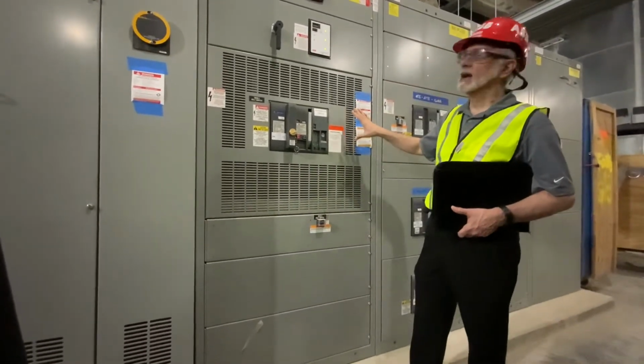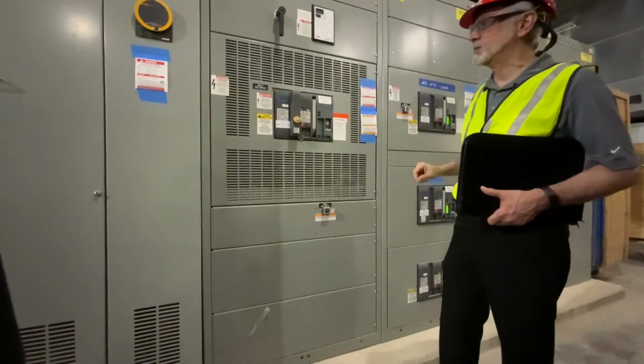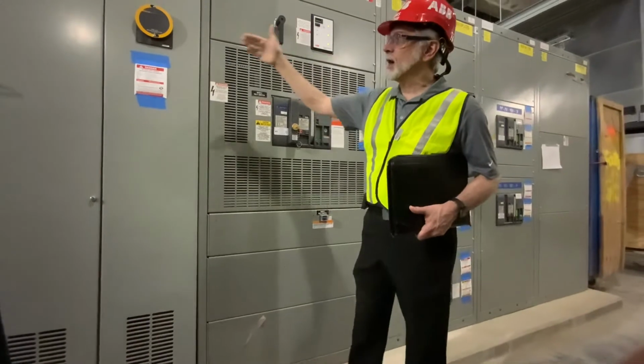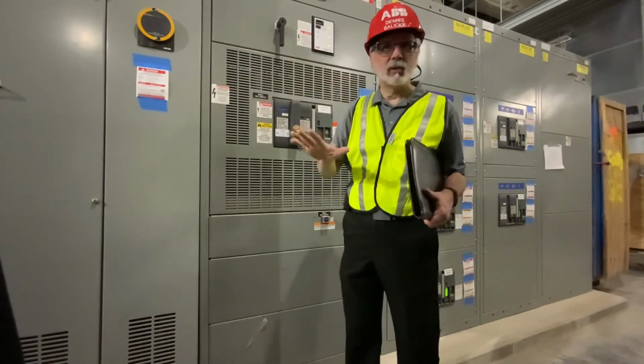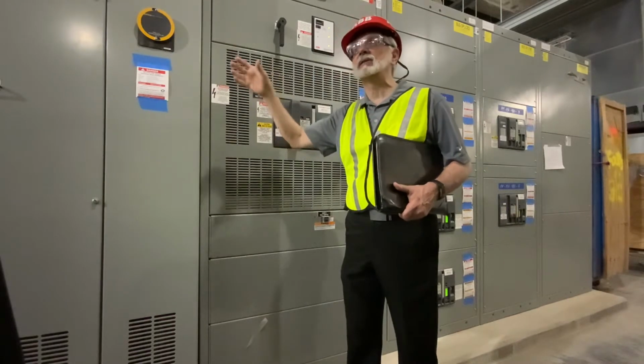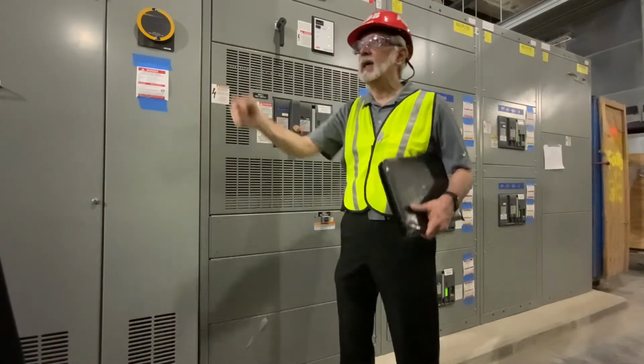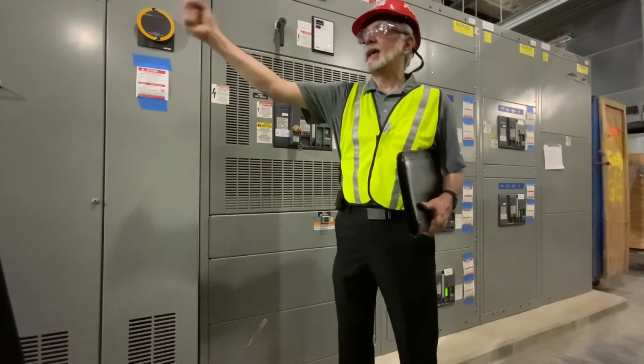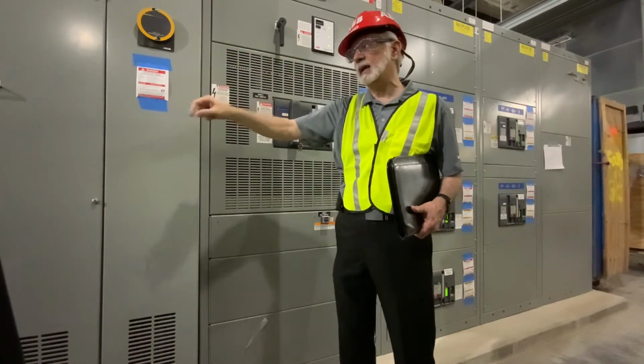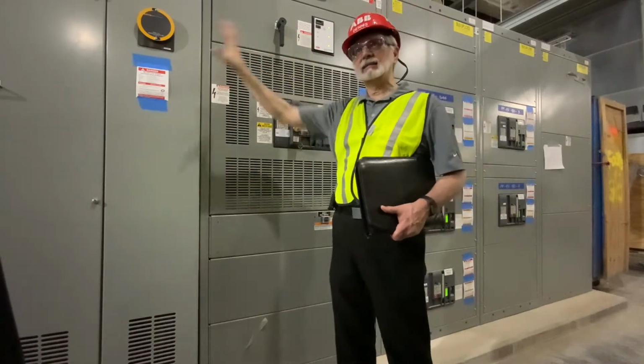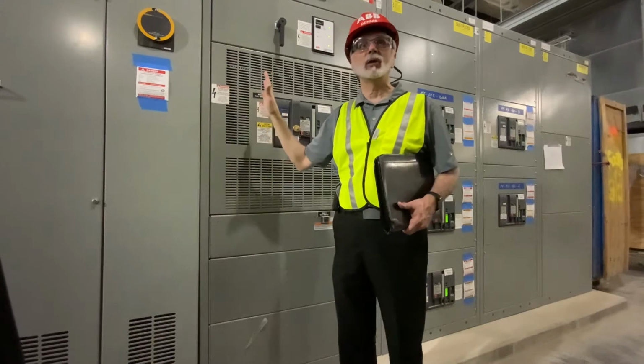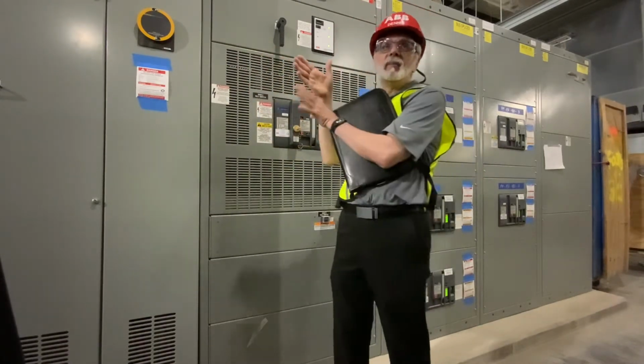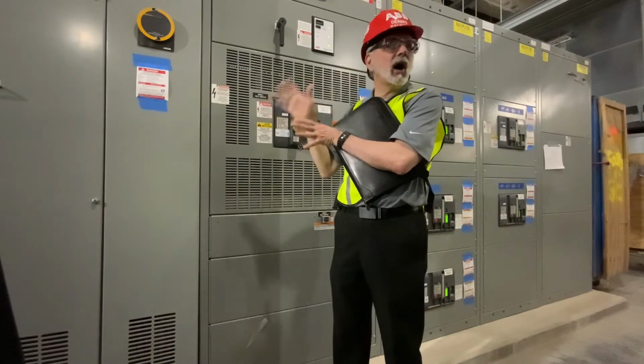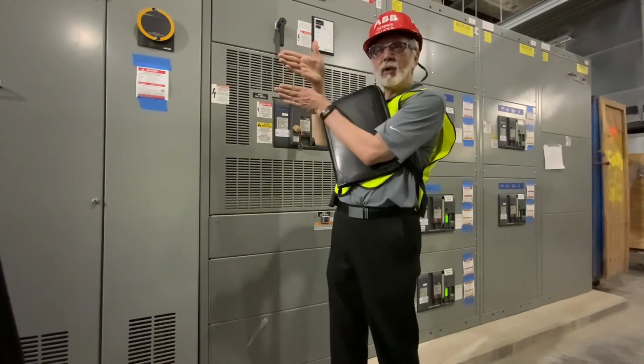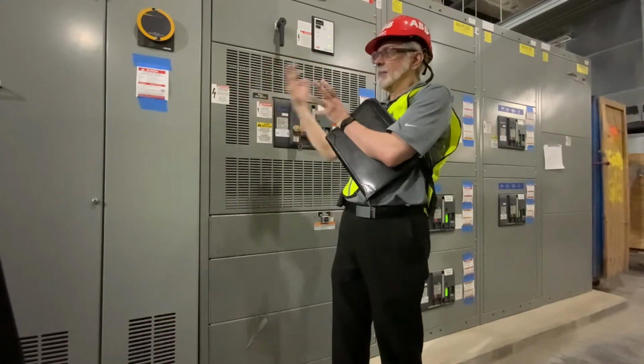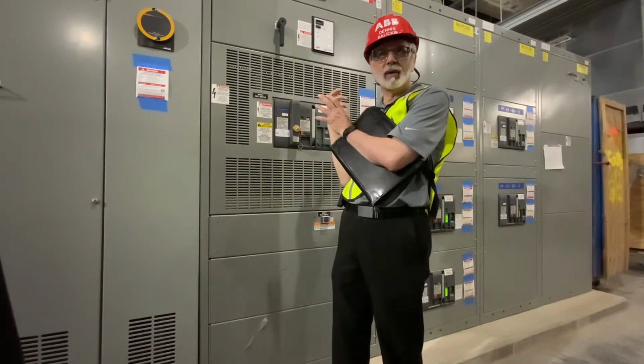Okay, so now we're down to the 480 volt part of the switchboard. Instead of having cables, which we've talked about so far on the medium voltage, where cables are coming into your main compartment, cables are coming up to your load interrupter switch, and cables are coming into the primary of your substation transformer, cables are not connecting these two pieces of equipment. What we use is something called flex braid. Basically we do that because transformers also have a tendency to hum and vibrate, and the flex braid eliminates passing that vibration on to the rest of the equipment downstream.